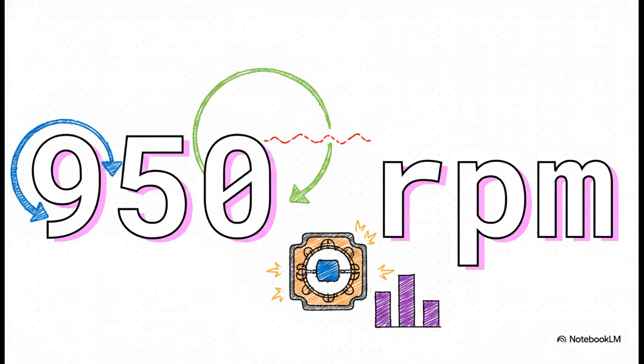That is our calculated rotor speed. First major victory in the bag. And honestly, this perfectly highlights a core rule of induction motors. Your physical rotor speed is basically always going to be just a little bit less than your synchronous speed. That 5% slip literally drags the 1,000 RPM theoretical max down to a real-world operating speed of 950 revolutions per minute.